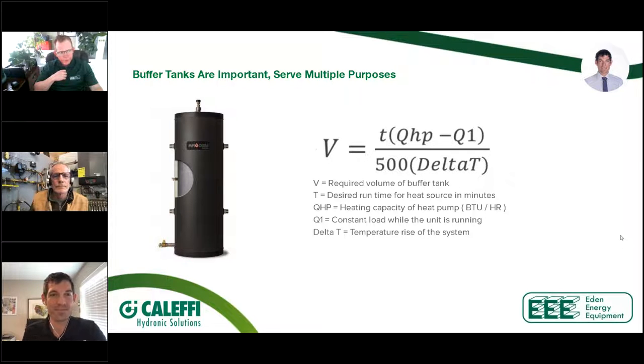Any thoughts on that, Bob? Yeah, no, that sums it up. Use the right formula for the equipment that you're connecting to it. Because what you'll find is if you have a modulating boiler, heat pump, whatever it might be, the tank gets a lot smaller. So you don't want to, like you say, buy a lot more tank than you need because you didn't size it for the low turndown or the lowest load that you're trying to buffer. So where he's going with this is with a boiler, if it's a 300,000 BTU boiler, we don't care. We care what is the low fire. We want to make sure we can accommodate for that.